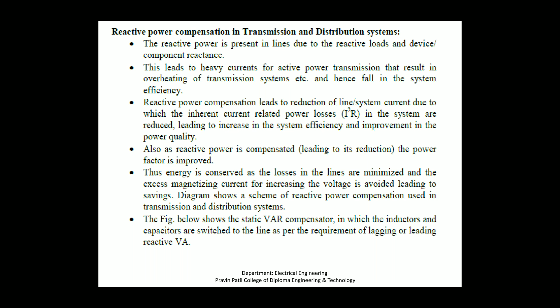The first is a transmission line, then next is a step down transformer, then a potential transformer, PT, for measuring the higher voltage. Then next is the thyristor module. The reduced voltage, the secondary side of the transformer, is connected to the thyristor module, which converts the voltage, first to DC, acting as a rectifier, and then to AC as an inverter. The output is connected to the capacitor banks and reactor banks, which act as a filter. Here is the controller which controls the voltage, the output of the thyristor.